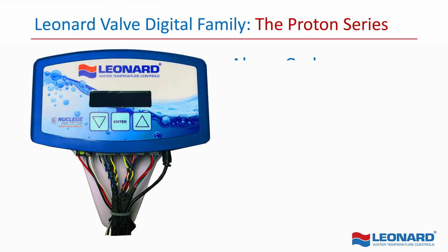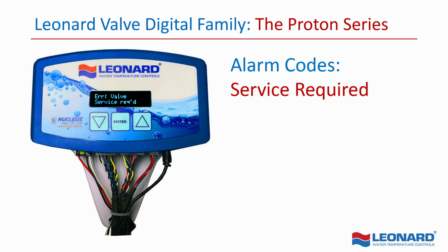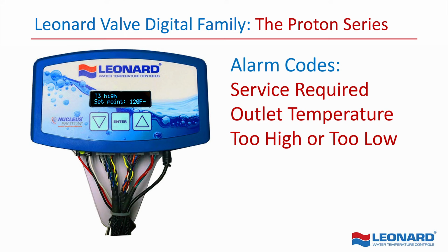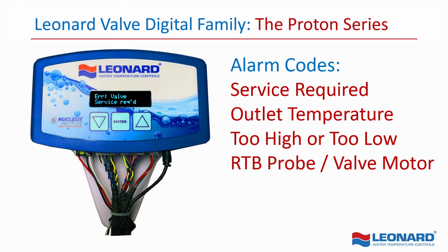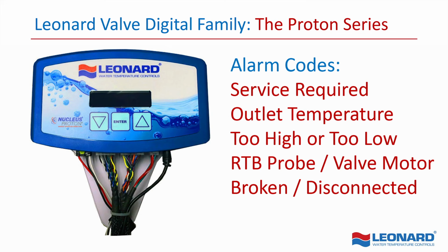Some of the possible alarms are going to be service required. That means the step count is below 90% of what the initial step count was, may just need to be cleaning the valve. The second alarm possible would be outlet temperature too high or too low. That also may require some cleaning of the valve. A third alarm would be RTD probe broken or disconnected, as well as valve motor broken or disconnected. The last alarm would be loss of power to the control box.